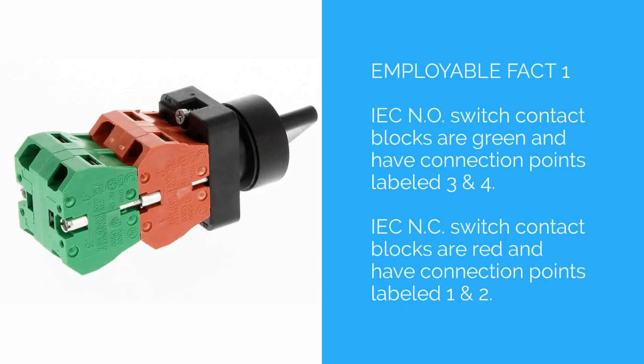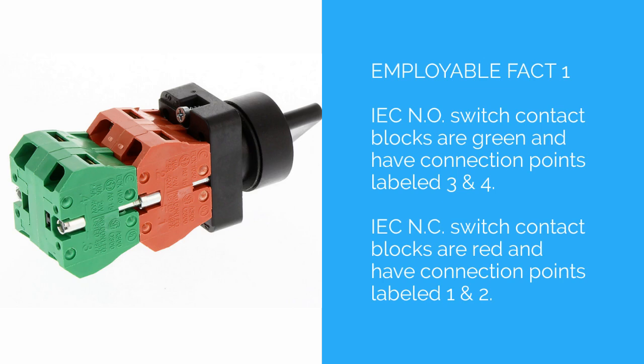Employable Fact 1: IEC normally open switch contact blocks are green and have connection points labeled 3 and 4. IEC normally closed switch contact blocks are red and have connection points labeled 1 and 2.